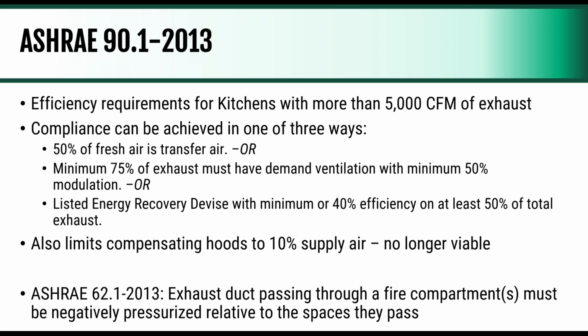The second way to meet that is 75% of the exhaust must have demand ventilation with the minimum 50% modulation, and that again is typically the easiest, and that's why we call it the demand control statute. And then the last option is a listed energy recovery device with a minimum of 40% efficiency must be on at least 50% of the total exhaust. Again, when we look through all of those options, we do find that demand control is the most effective option and the cheapest way to get it to be compliant with ASHRAE 90.1.